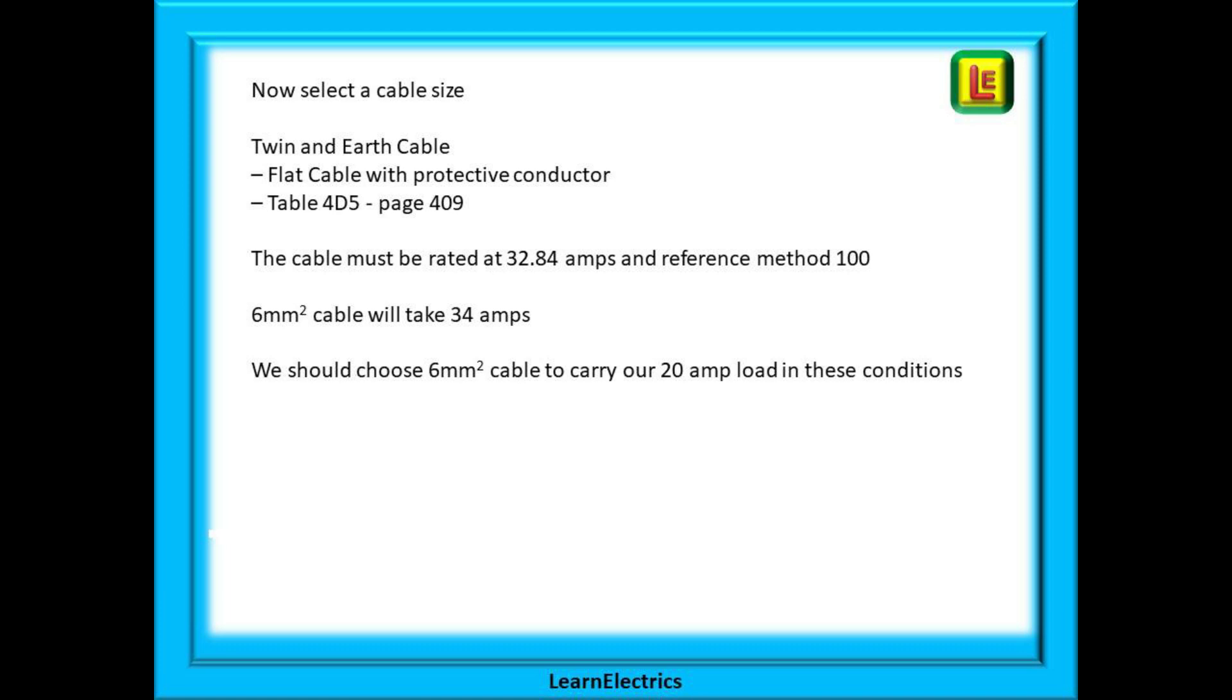Now select a cable size. We know it is twin and earth cable which is called flat cable with a protective conductor. This is table 4D5 and is found on page 409. The cable must be rated at 32.84 amps and reference method 100 must be used. And we find that 6mm cable will take 34 amps. Therefore we should choose 6mm cable to carry our 20 amp load in the given conditions.